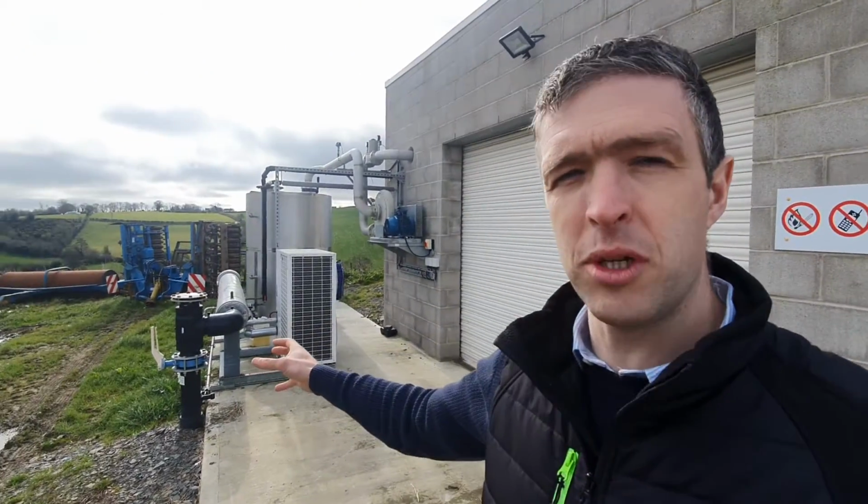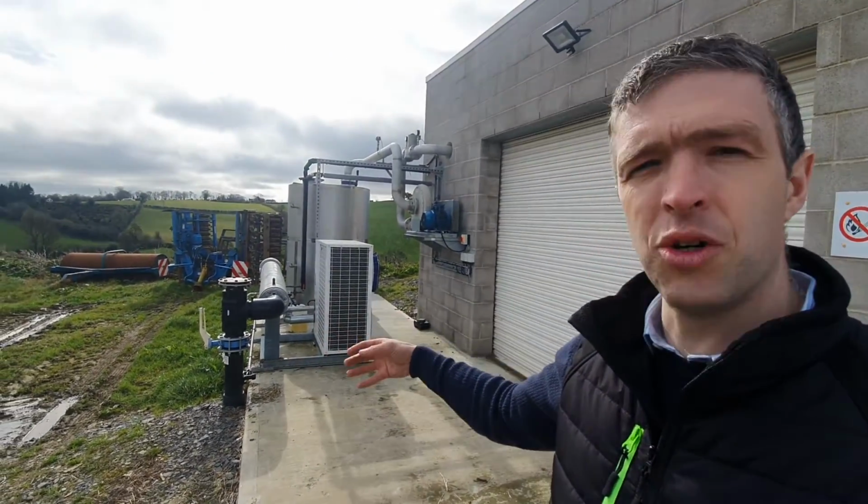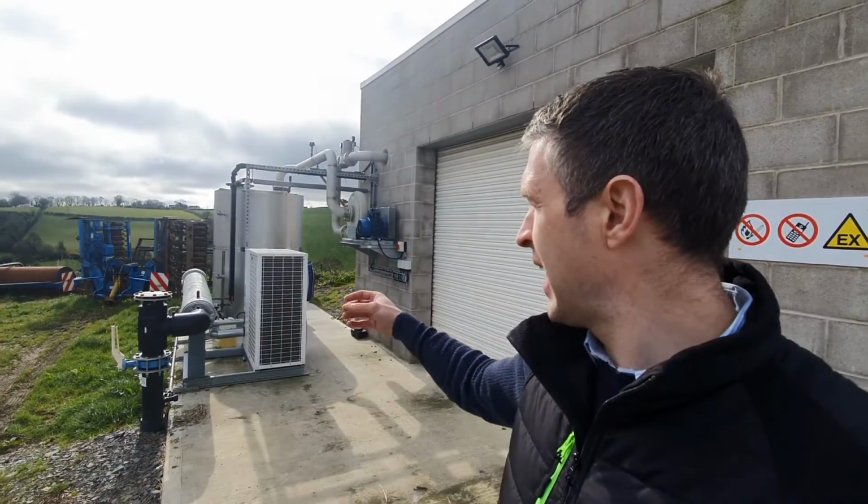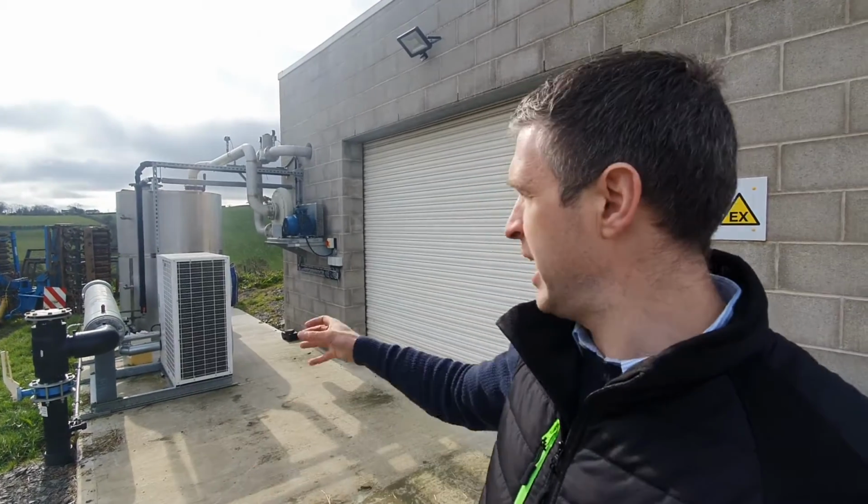Gas conditioning skid, which basically cools the gas to remove any moisture, reheats the gas, and puts it through a carbon bed to take any of the contaminants out of the gas, which on an agriculture-based plant is very, very little. You have a small amount of H2S and a few other contaminants. Okay. From there the gas goes into an engine inside.